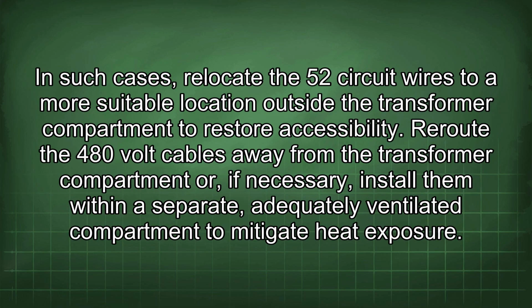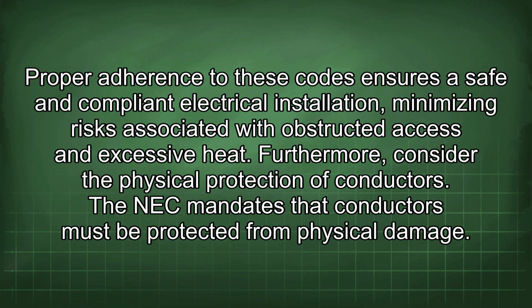In such cases, relocate the 52 circuit wires to a more suitable location outside the transformer compartment to restore accessibility. Reroute the 480-volt cables away from the transformer compartment or, if necessary, install them within a separate, adequately ventilated compartment to mitigate heat exposure. Proper adherence to these codes ensures a safe and compliant electrical installation, minimizing risks associated with obstructed access and excessive heat.